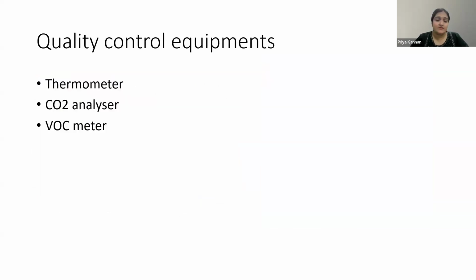Then, is this all that you need to have? Any machine needs to be checked on a daily basis or on a regular basis. So, even if it is not mandated in the ART law, quality control equipment is mandatory for every embryology lab, for which you need a thermometer, to measure the temperature in the incubators, and B, to measure the temperature on all your working surfaces also. You need to have a CO2 analyzer. If you are using a benchtop incubator with trigas, you need to have a CO2 plus O2 analyzer as well. Both come in the same one.